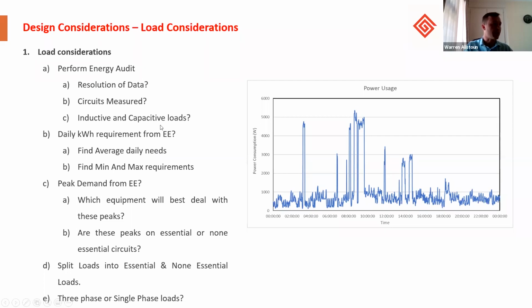So inductive and capacitive loads will need to be put onto the non-essential side. GoodWe products do not support inductive and capacitive loads with large start currents. These types of circuits, like air conditioners and massive pumps, need to be installed on the non-essential side to ensure that the inverter and batteries are not overloaded.